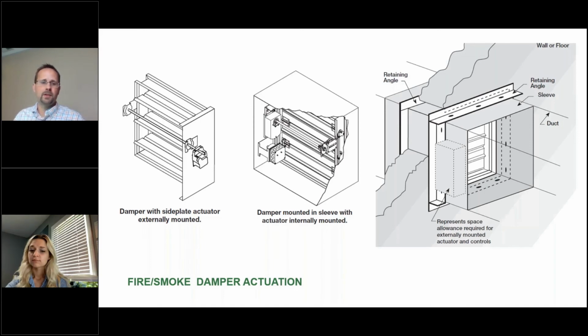There are a couple of different locations for actuators. Actuators need to be accessed for maintenance, and we need to make sure that maintenance access is maintained. It really takes about 6 inches or so on the side, because you'll see a shaft and you have to be able to pull that actuator off the shaft. In a lot of healthcare, you'll have ducts stacked against walls, and so that can sometimes be overlooked. And it's an issue when the owner has to do maintenance on that actuator.